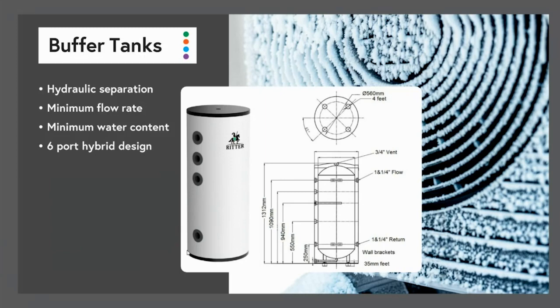Now, what it does is it allows the heat pump and the boiler to complement each other rather than compete with each other for the volume of the tank, because the flow from the heat pump becomes the return to the boiler. So the boiler is only doing the top up required to keep the system on temperature, and it's not either meeting the full load or competing with the heat pump to heat the cylinder. And so with good control, that can be a very cost-effective system where the heat pump may be doing maybe upwards of 80% of the load, and the peak load conditions, which don't happen very often at all, can then be covered by the boiler.